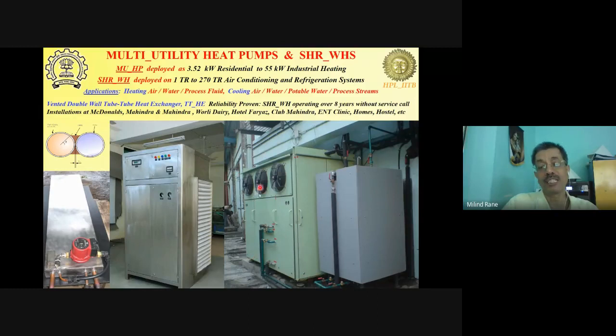Moreover, this unit was capable of saving around 25 to 36% of the power required by just the air-cooled chiller, which was earlier deployed in that location. And the power consumed by the fans in this case was around 1/9 of that of the conventional air-cooled chiller. And this we were able to do using an evaporatively cooled condenser. So instead of an air-cooled condenser, we have a technology called rotating contacting device or diabatic contacting device. And that enabled us to evaporatively condense the refrigerant.